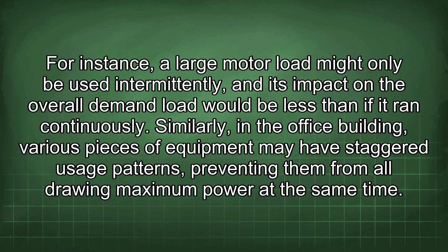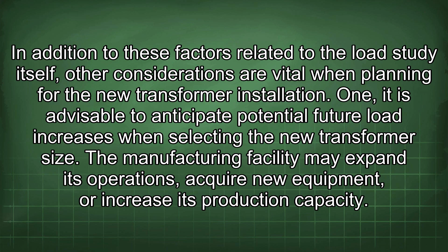In addition to these factors related to the load study itself, other considerations are vital when planning for the new transformer installation. 1. It is advisable to anticipate potential future load increases when selecting the new transformer size. The manufacturing facility may expand its operations, acquire new equipment, or increase its production capacity. The office building may add more workstations, install new servers, or upgrade its HVAC system. Planning for future growth ensures that the transformer has adequate capacity to handle increased demand without becoming overloaded.